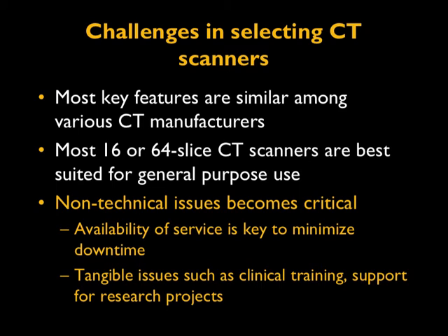However, the non-technical issues become very critical in selecting the CT scanner. First and foremost, to minimize downtime, it is important to ensure that the availability of service is good. I have seen situations where a remotely located clinic will acquire an exotic new CT scanner.